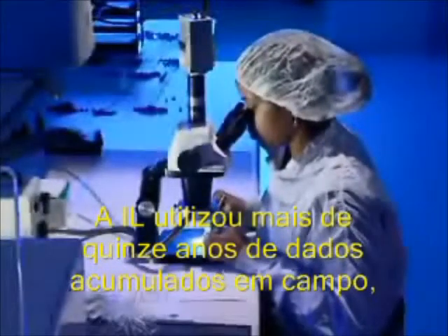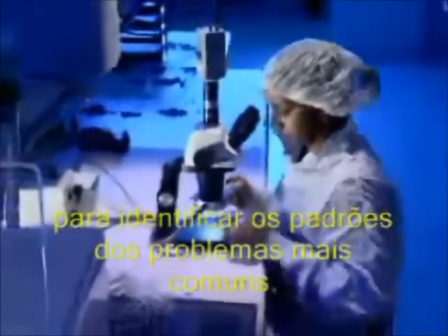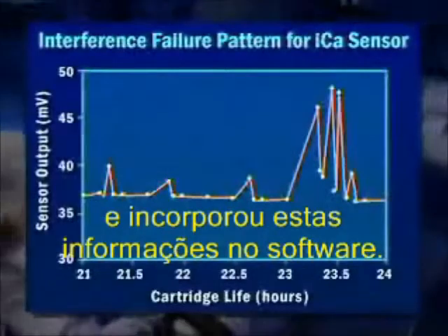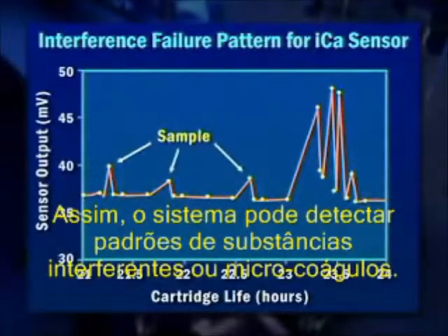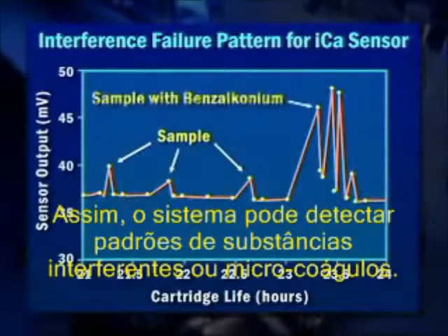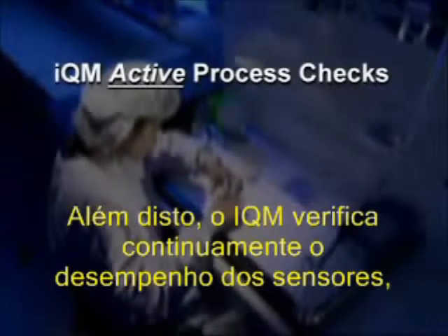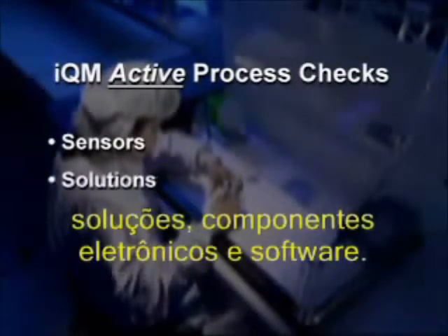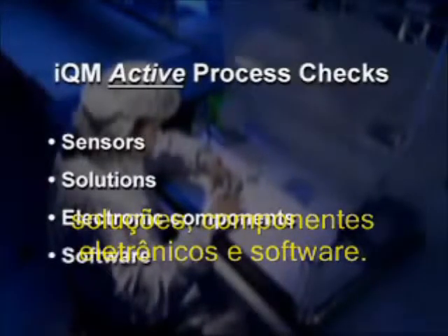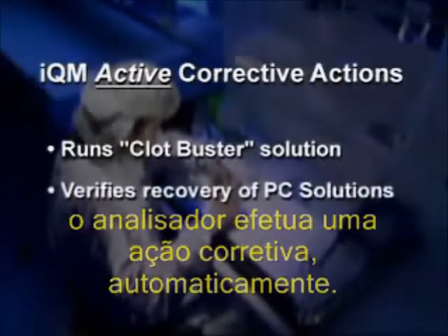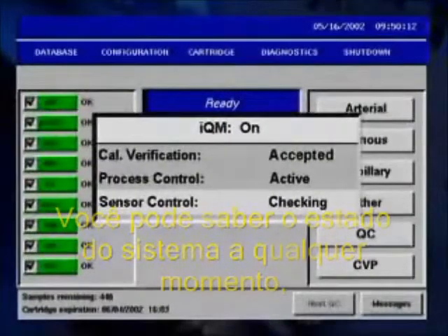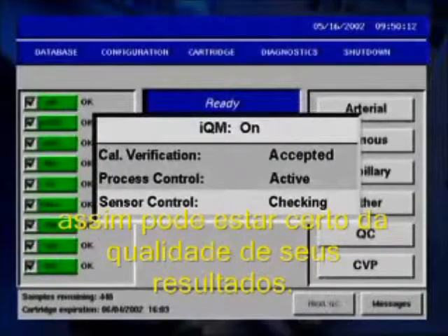Instrumentation Laboratory has used over 15 years of accumulated data to define the performance patterns for the most common problems and has incorporated this knowledge into the software. Thus, the software is able to detect patterns such as interfering substances or microclots. In addition, IQM conducts continuous active process checks to monitor performance of sensors, solutions, electronic components, and software. And if any system check fails, the analyzer automatically takes corrective action, so you don't have to. The easy-to-use system lets you know the status at all times, so you can be assured of quality results.